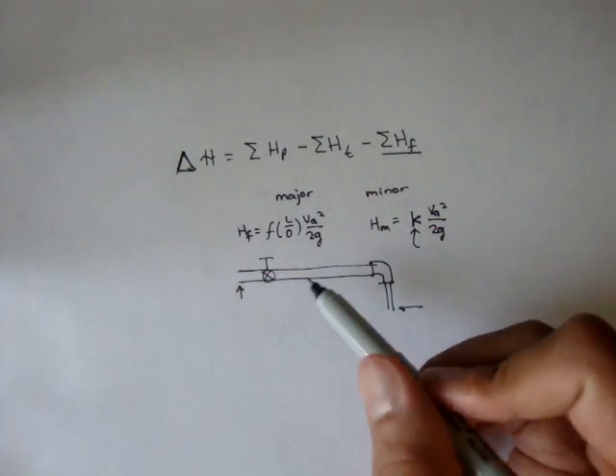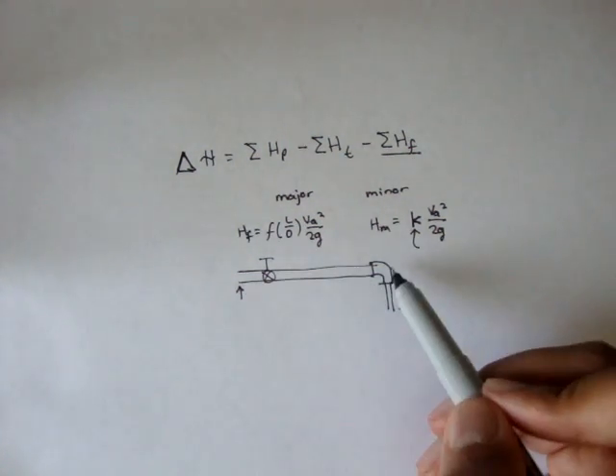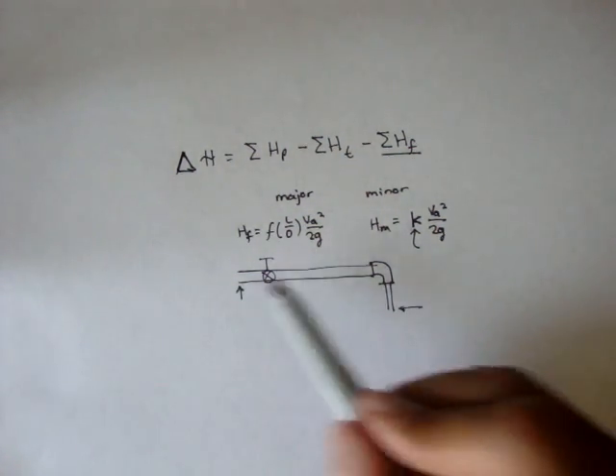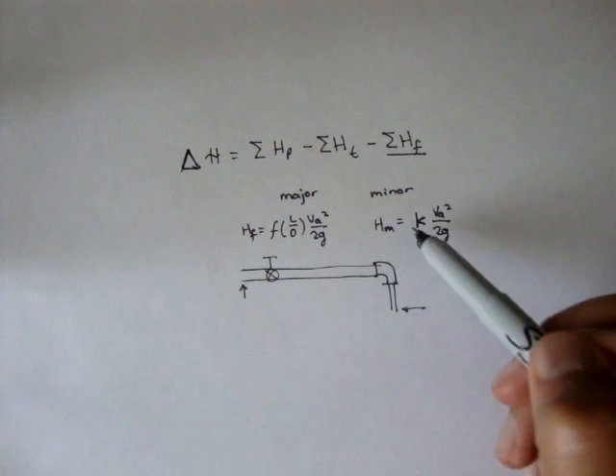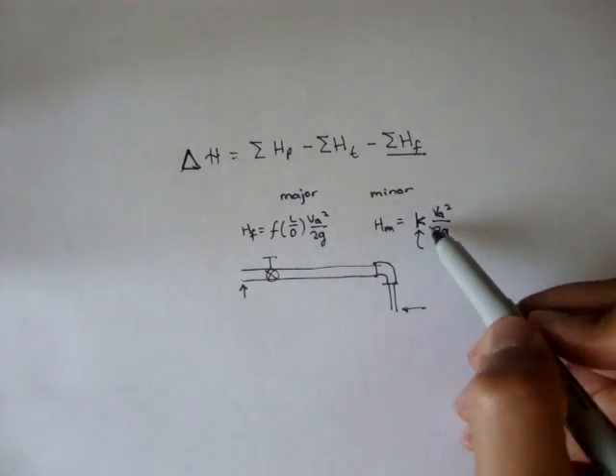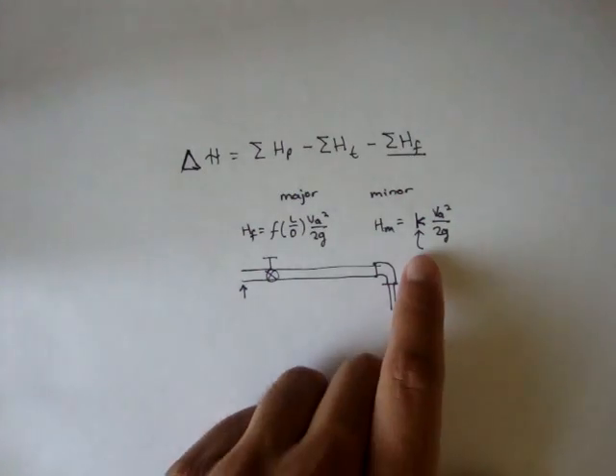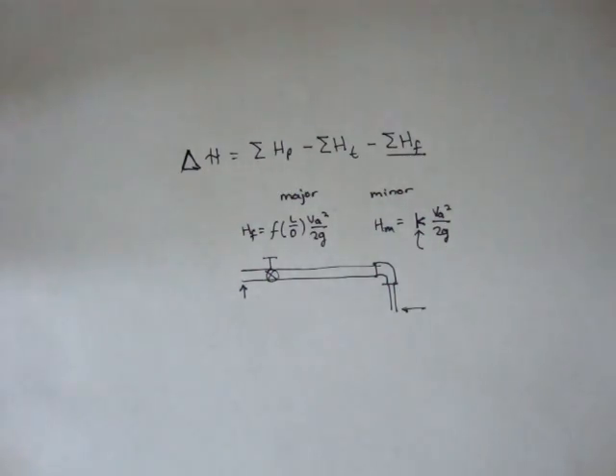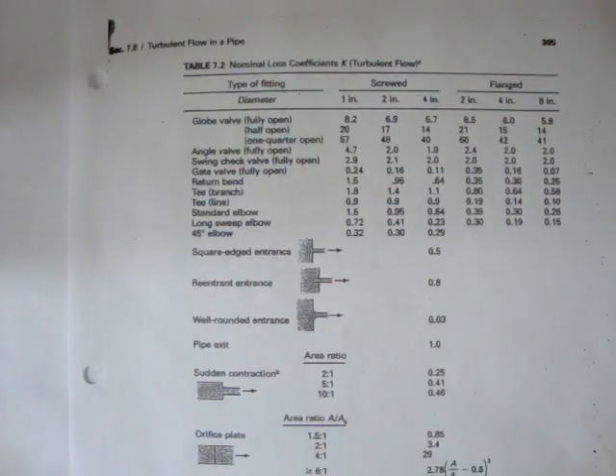And for each one of those devices, the elbows, the turns, the entrance, the exits, we summate all the major and minor losses. And for all the minor losses, we use this formula K times VA squared over 2G. Now, in order to figure out what that K is, we come to this table, and this table, every book is different, this is just the table for my book.